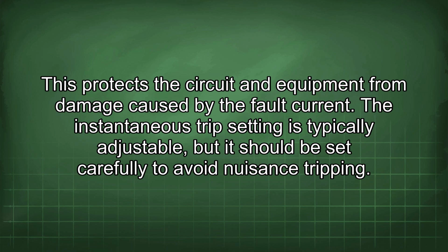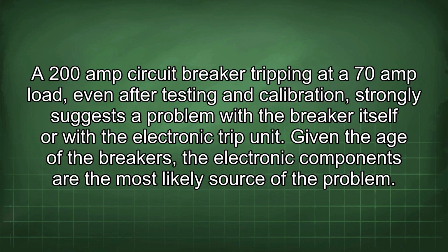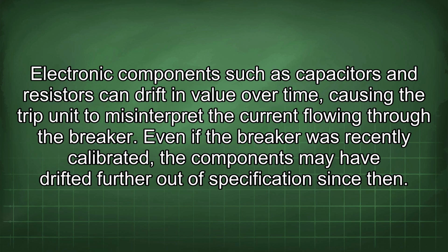The instantaneous trip setting is typically adjustable, but it should be set carefully to avoid nuisance tripping. A 200 amp circuit breaker tripping at a 70 amp load, even after testing and calibration, strongly suggests a problem with the breaker itself or with the electronic trip unit. Given the age of the breakers, the electronic components are the most likely source of the problem. Electronic components such as capacitors and resistors can drift in value over time, causing the trip unit to misinterpret the current flowing through the breaker. Even if the breaker was recently calibrated, the components may have drifted further out of specification since then.